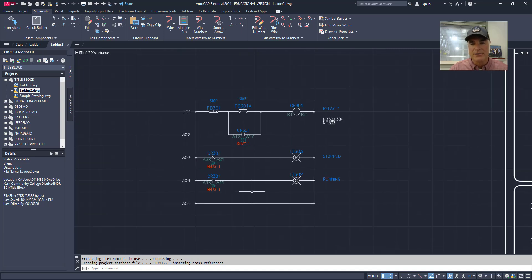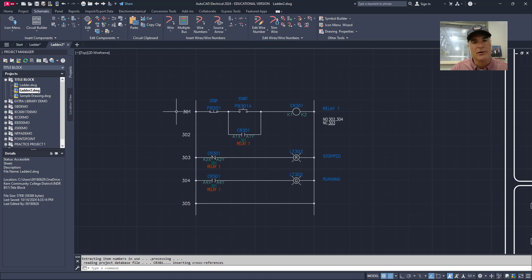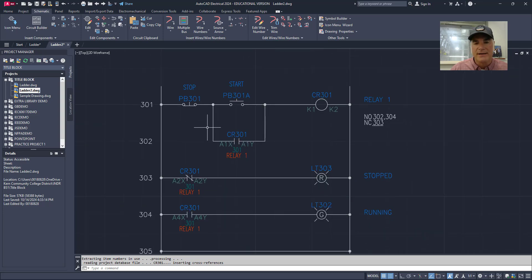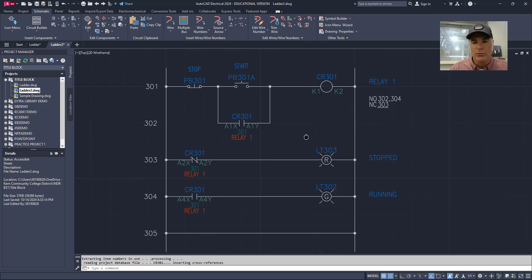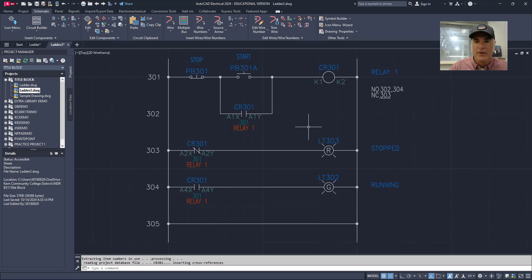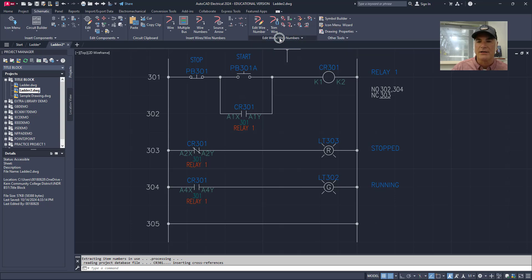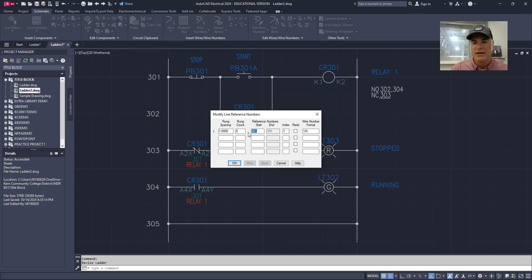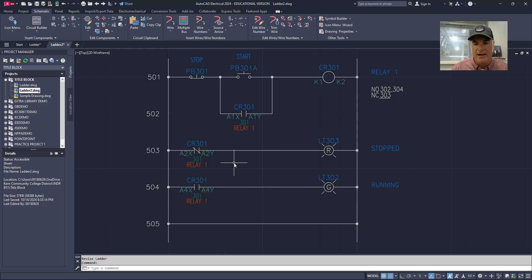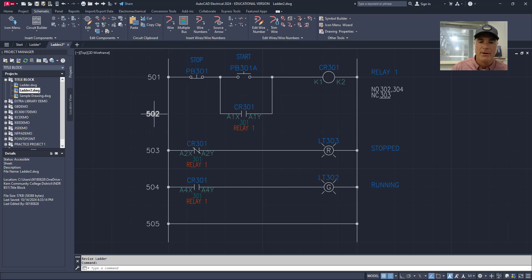Let's say that I wanted to renumber this entire ladder. So instead of starting with 301 I wanted it to start with 501. Well that also means that all of the components in this ladder need to be revised as well. And the revised ladder tool will do that. So I'll go to edit wires and wire numbers and revise ladder. I don't want to change the spacing, I don't want to change the rung count, but I do want to change this reference number from 301 to 501. So I'll choose okay on that. You'll see that it updates my reference numbers here, but it has not updated any of these numbers here.